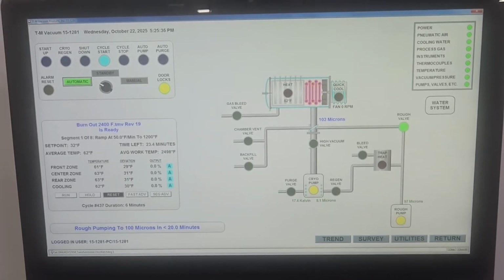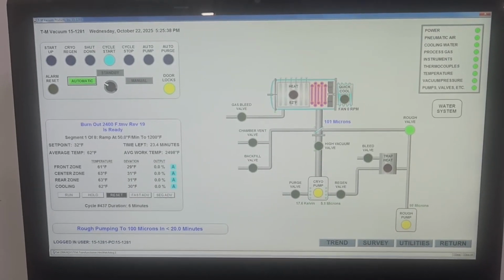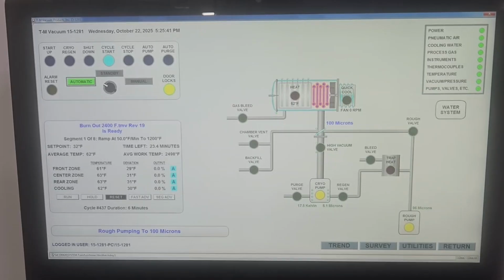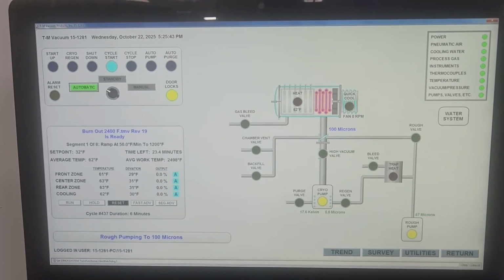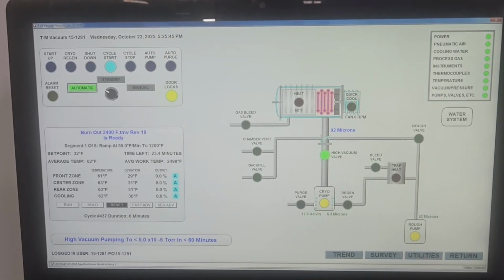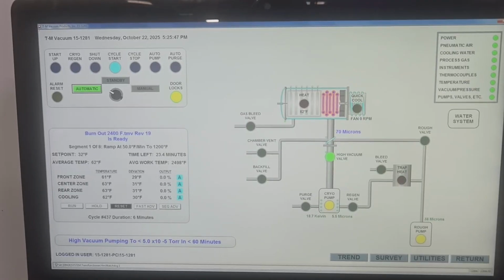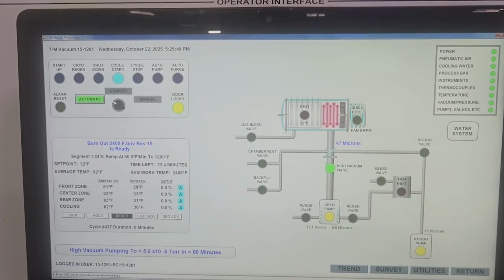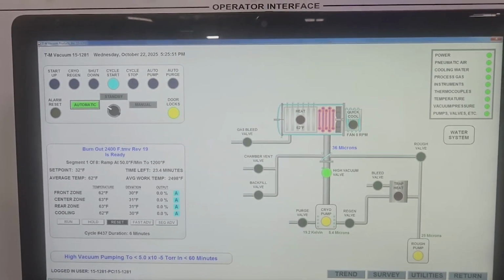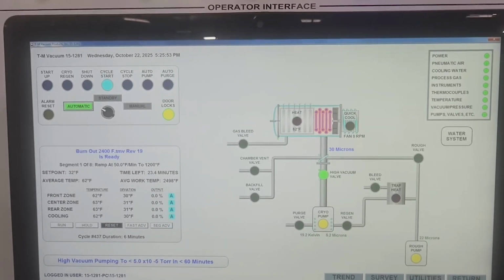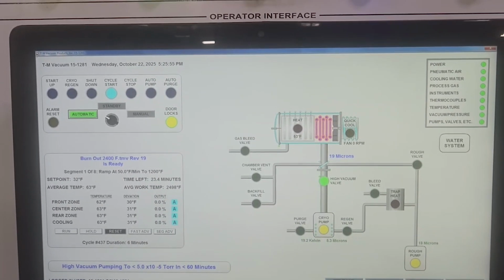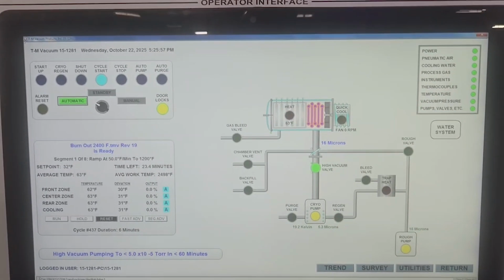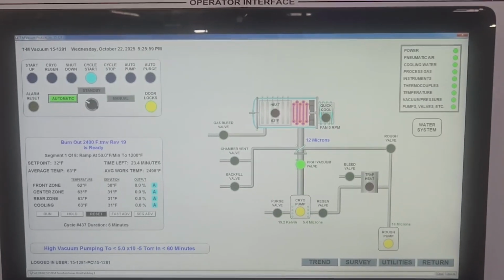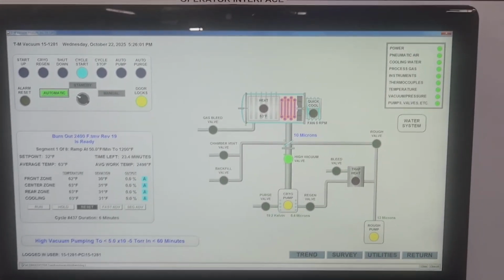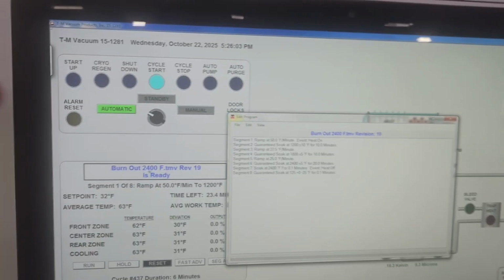The microns are approaching the 100 mark. The high vacuum valve is opened and now it's pumping down additionally with the assistance of the cryo pump. We're running a burnout program. We're not brazing anything right now. We're doing our maintenance burnout.